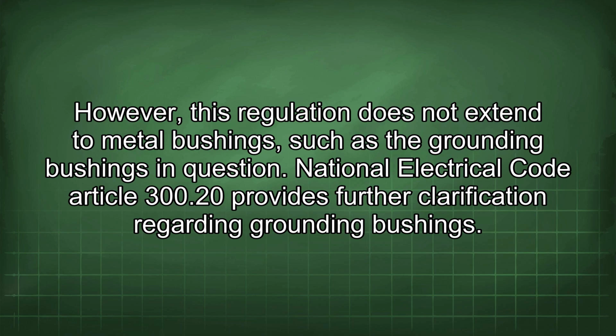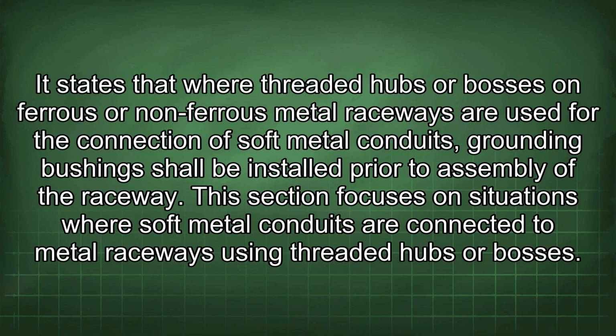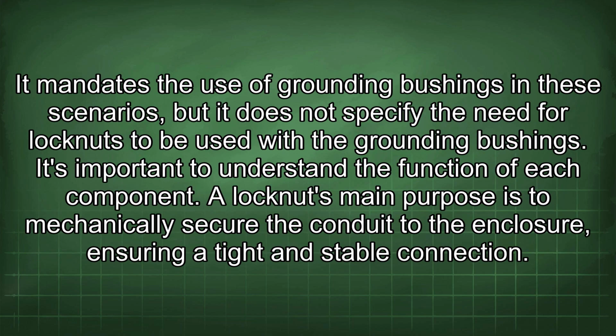National Electrical Code Article 300.20 provides further clarification regarding grounding bushings. It states that where threaded hubs or bosses on ferrous or non-ferrous metal raceways are used for the connection of soft metal conduits, grounding bushings shall be installed prior to assembly of the raceway. This section focuses on situations where soft metal conduits are connected to metal raceways using threaded hubs or bosses. It mandates the use of grounding bushings in these scenarios, but it does not specify the need for locknuts to be used with the grounding bushings.